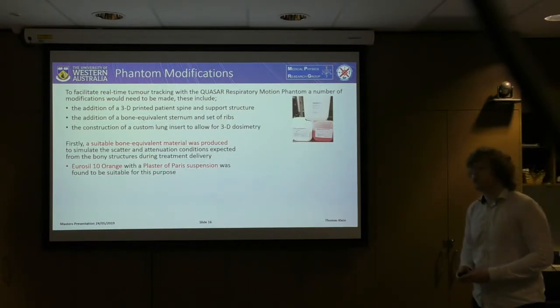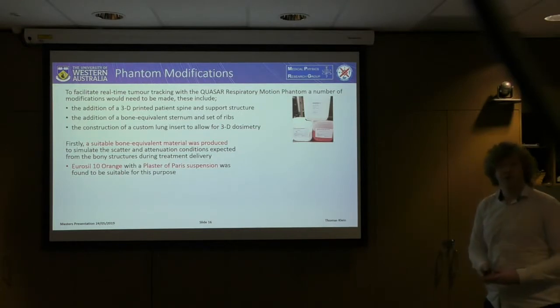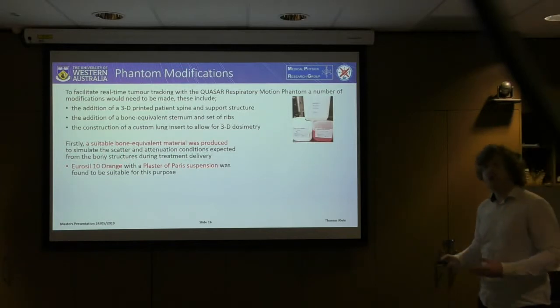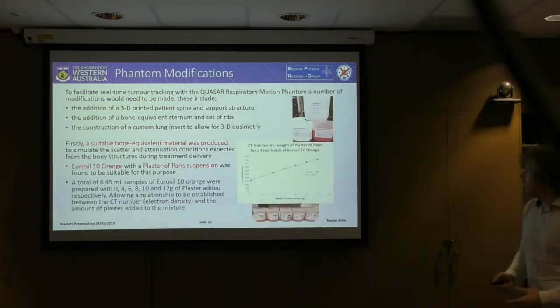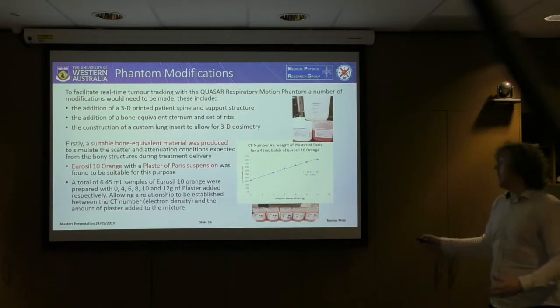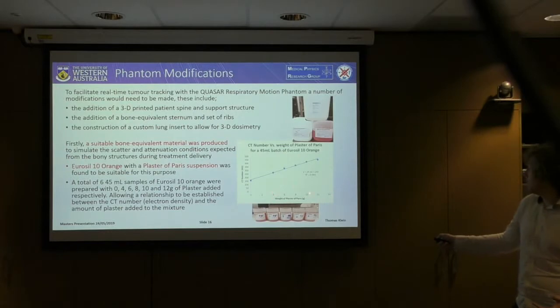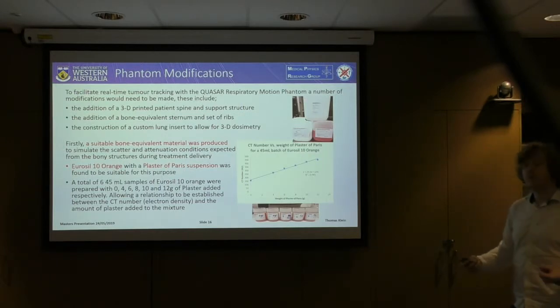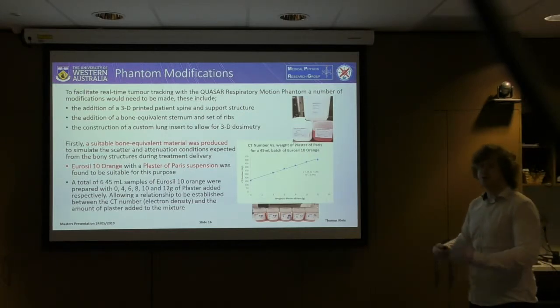We needed to produce a material equivalent to bone to simulate the scatter and attenuation conditions created by real bony structures in a patient. For this purpose, we used Eurosil 10 Orange, commonly used to make bolus material, with the addition of a plaster of Paris suspension. We took six different samples and added varying amounts of plaster to determine a relationship between the amount of plaster and the electron density in terms of CT number, allowing us to prepare a flexible bone-equivalent material with any required electron density.